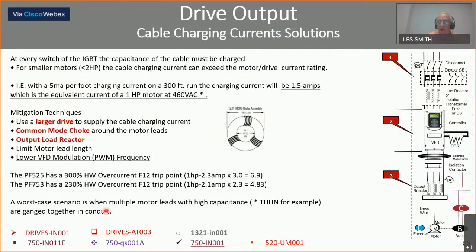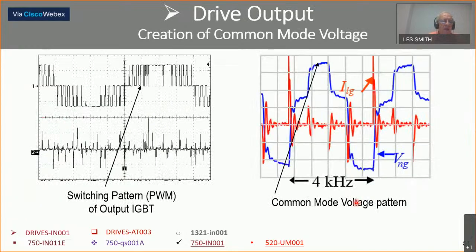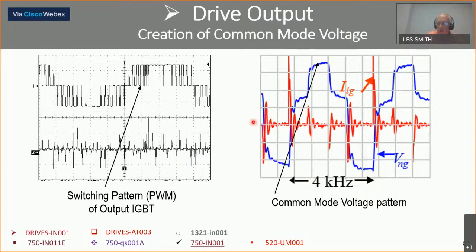Here's a waveform showing the PWM and the common mode voltage. The problem is the fast rise time — this is more vertical these days than it used to be. We used to have milliseconds; now we have nanoseconds in switching speed. So our problems are worse than they were yesterday, and will likely be worse tomorrow as switching speeds continue to increase.